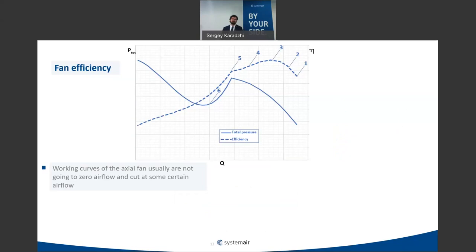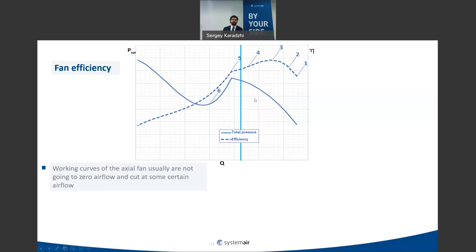Here is an example of the curve of an axial fan with a high pitch angle installation. You can see the efficiency curve and the total pressure curve. In any catalog, axial fan curves are cut at some point — you don't see the full curve as you would for centrifugal fans with backward curved blades. This is because beyond that cut-off point there is a very problematic region, and the curve is cut to provide a safety margin and avoid operating in stall.